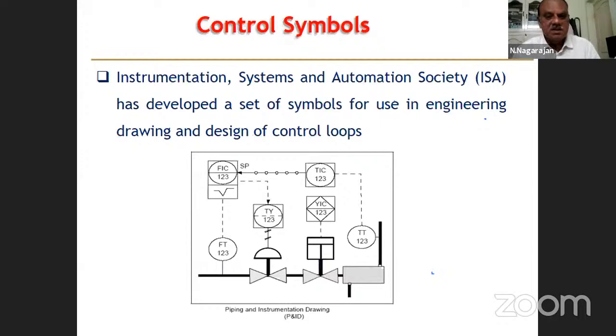So instrumentation uses a lot of symbols. I will quickly run through them, because this itself is another topic. In instrumentation and the P&IDs, piping and instrumentation diagrams, we use a lot of symbols for the control system. Usually the measured variable is in the field, and a circle is shown, FT 123. In a control loop, you will see the same number is maintained. This control loop has a serial number of 123. That means flow transmitter, FT123.